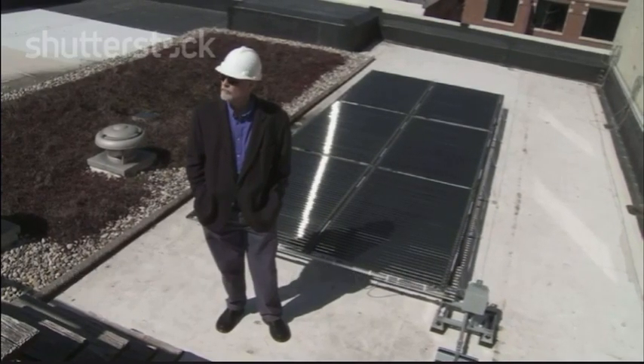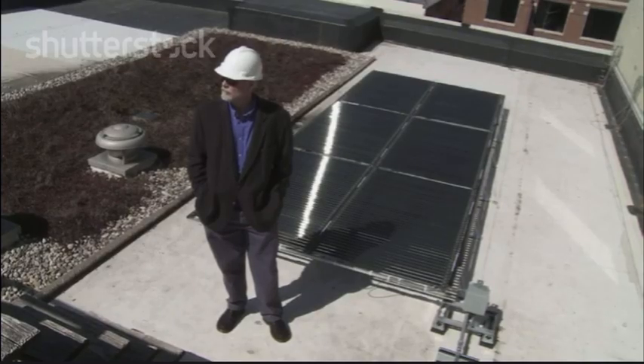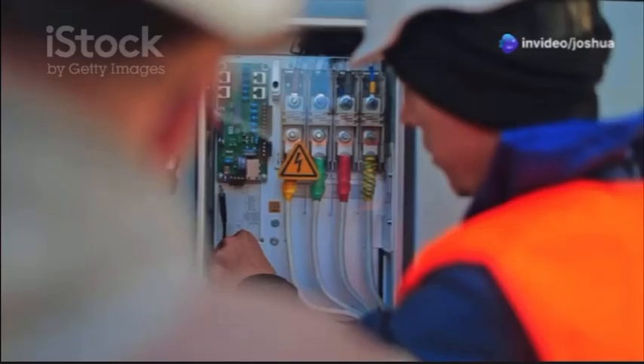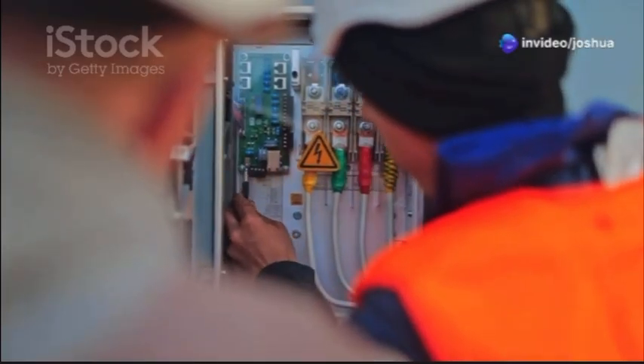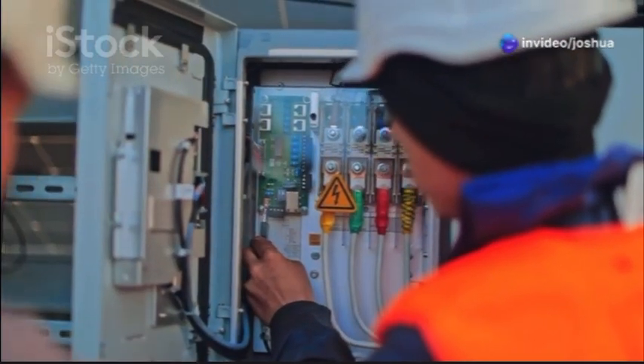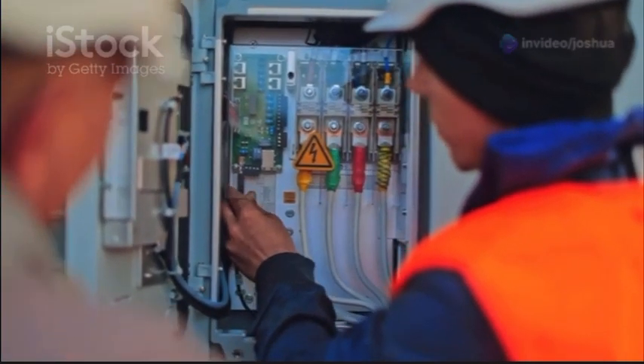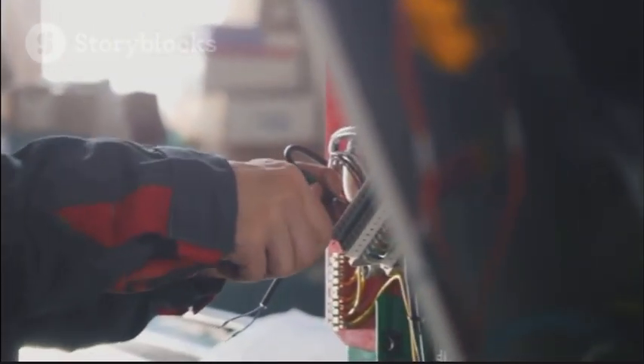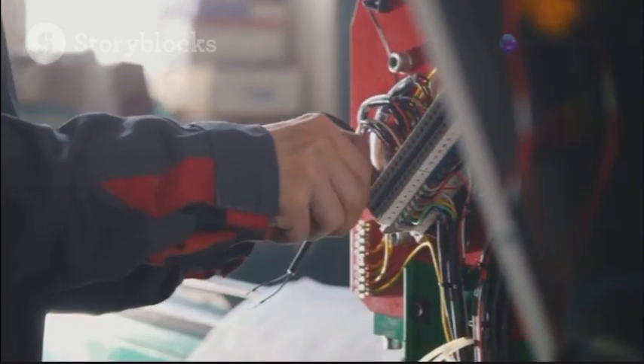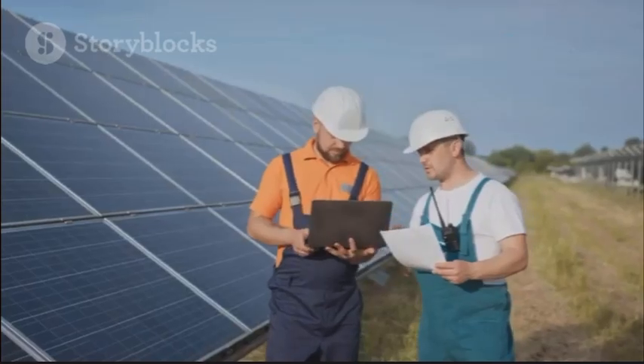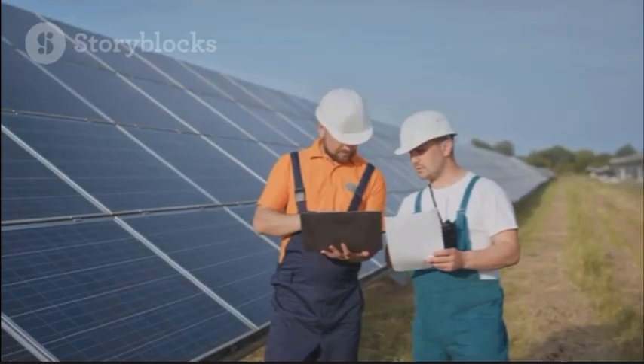With the installation complete, it's time for the moment of truth, firing up your solar power system. But before you start popping champagne corks, we need to make sure everything is working correctly. Step 1. Visual inspection. Double-check all connections, wiring, and grounding to ensure everything is secure and properly installed. Step 2. Power up. Turn on the circuit breaker for the solar inverter at the main electrical panel. Step 3. Inverter activation. Follow the manufacturer's instructions to activate and configure the inverter.